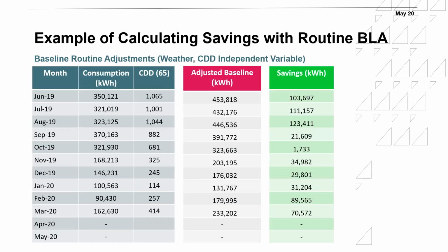Now, let's say I did the changes, right? And I have now the bills for the reporting period. So for the reporting period consumption, I've done the adjustments or the energy conservation measures in May 2019, and I started collecting data of how much I'm using in June 2019 and onwards. As you can see here, the consumption per month has been collected from the utility bills. Now I need to look at that particular reporting period to see what the cooling degree days are in that reporting period and see if I need to do any adjustments for the baseline based on that.